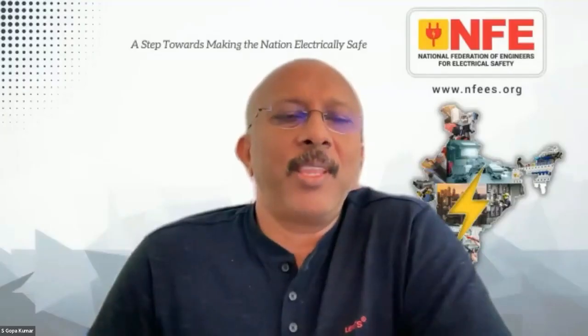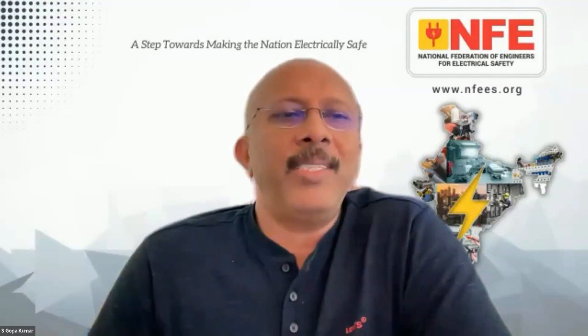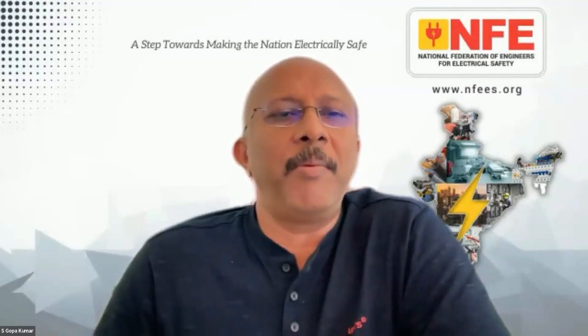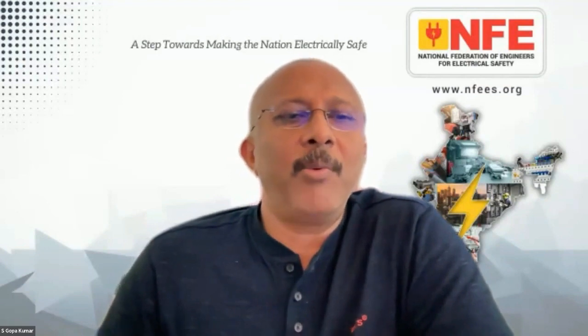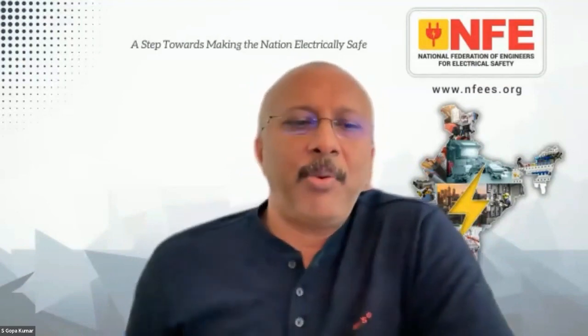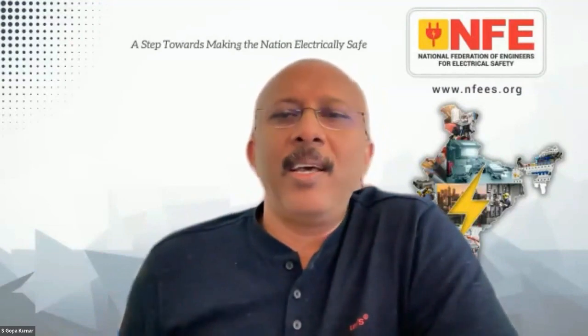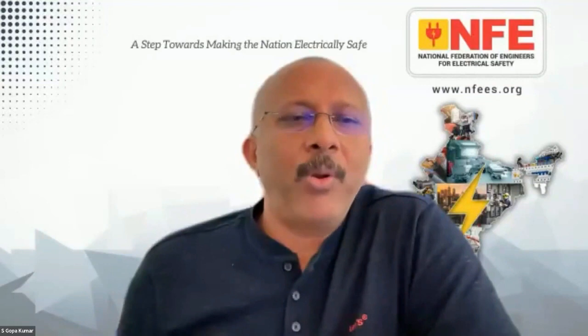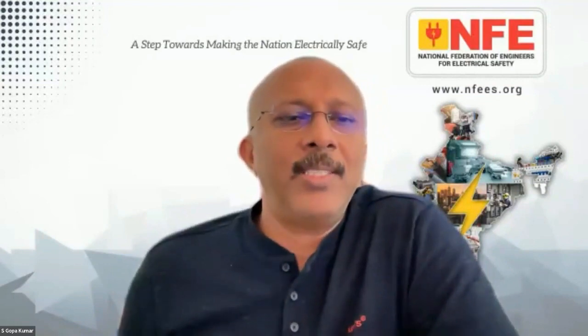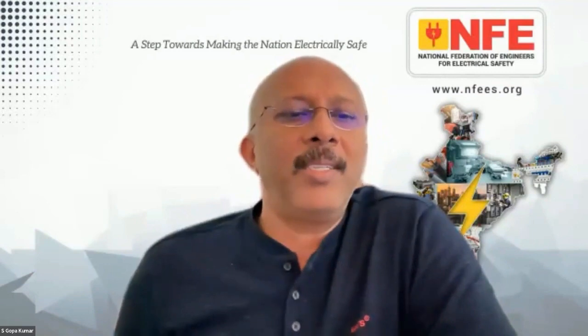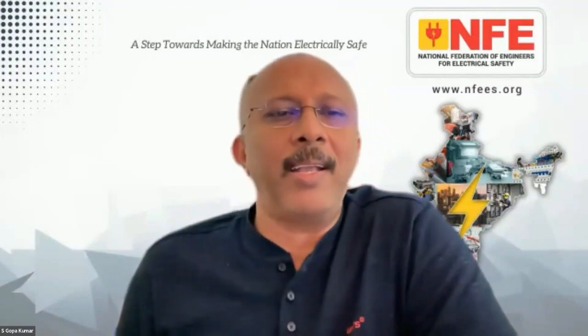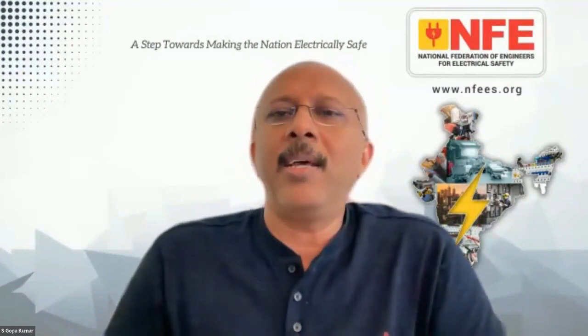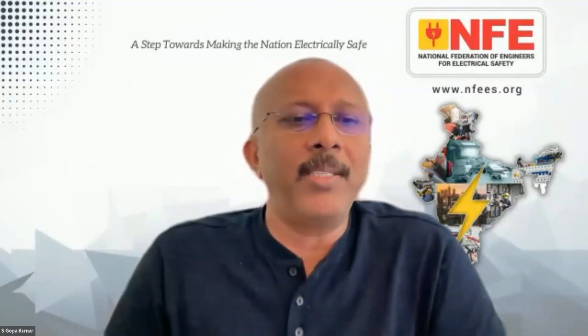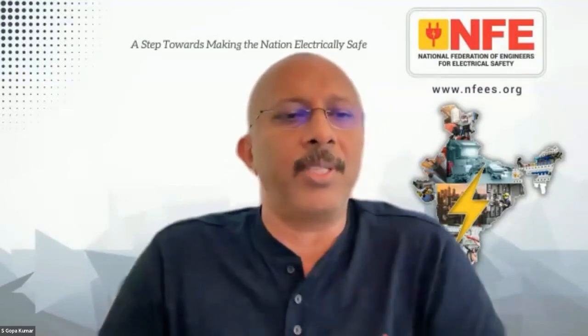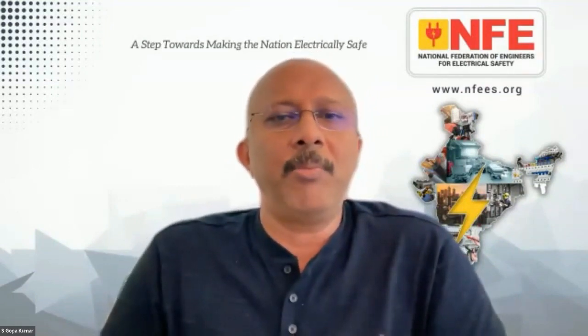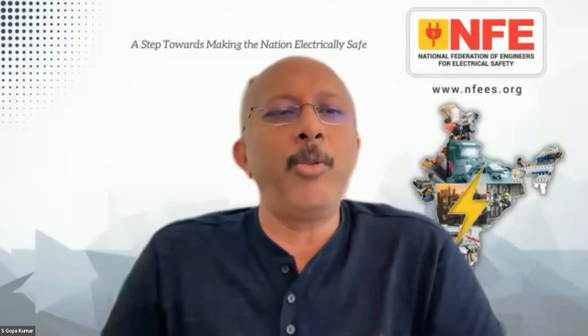I've been taking classes for the last 25 or 26 years on this subject all over India. Maybe if I count, probably more than 1,000 classes I have taken. Still, the problem is, first of all, the question, say, for example, lightning arrestor. What do you mean? Do you mean a distribution surge arrestor or a lightning air termination system in a building? This is the first question to be asked back, because in the standards regulation, there is a mistake in regulation number 74.